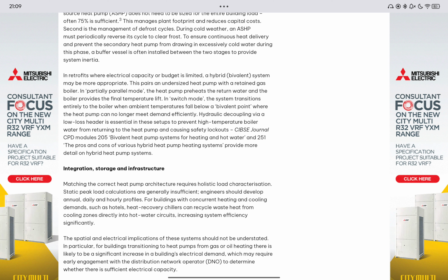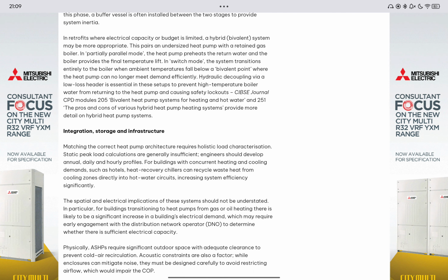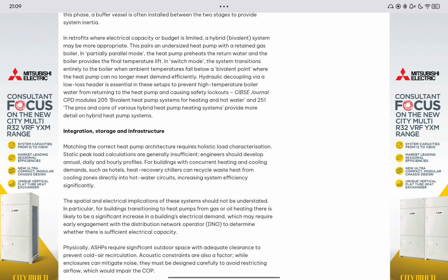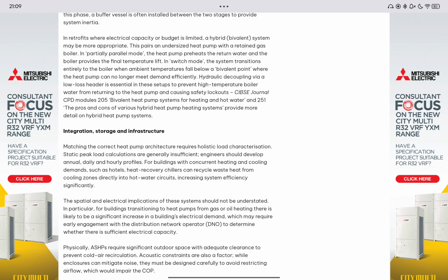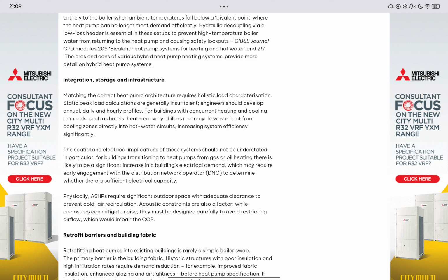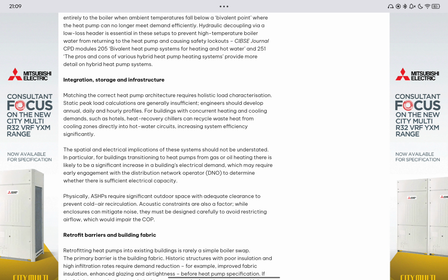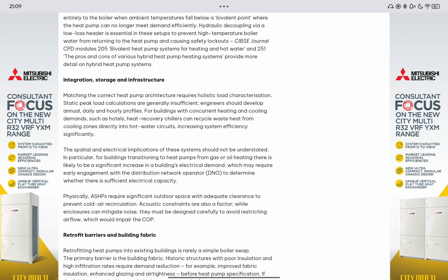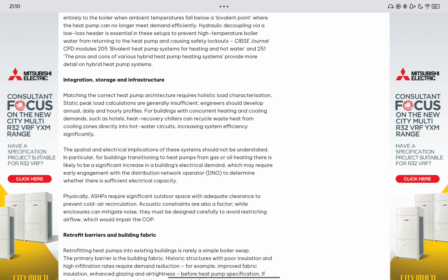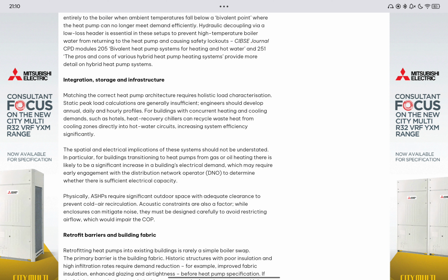CIBSE Journal CPD Module 205, Bivalent Heat Pump Systems for Heating and Hot Water, and 251, The Pros and Cons of Various Hybrid Heat Pump Heating Systems, provide more detail on hybrid heat pump systems. Integration, storage and infrastructure. Matching the correct heat pump architecture requires a holistic load characterization. Static peak load calculations are generally insufficient. Engineers should develop annual, daily and hourly profiles.